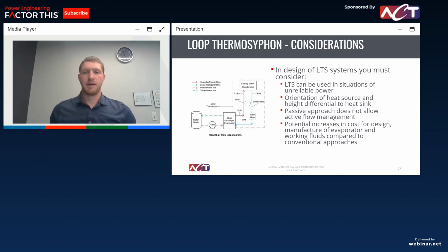So when you're looking at if a loop thermosyphon is feasible, that's certainly the most important thing there: if you can have your heat sink located above your evaporator. The passive approach doesn't allow active flow management. So with a pump solution, you can control that pump, make sure you're pumping the exact amount of, however many gallons per minute you want of that fluid.